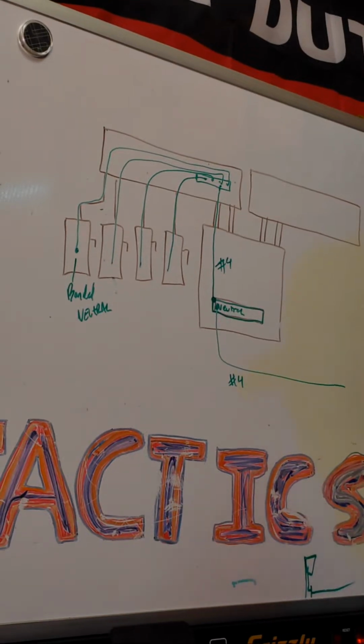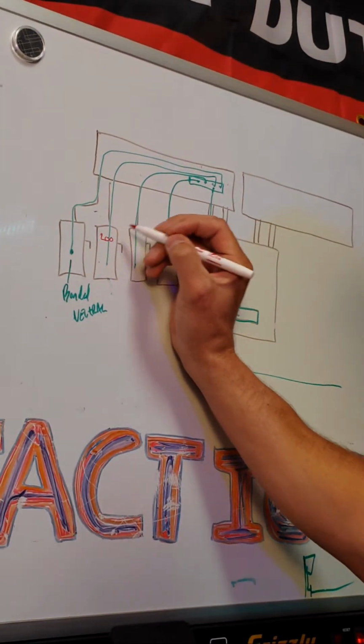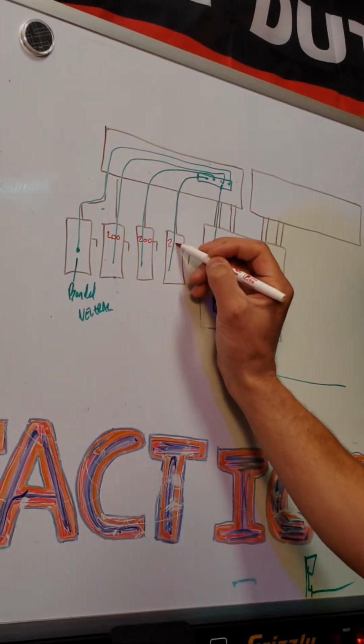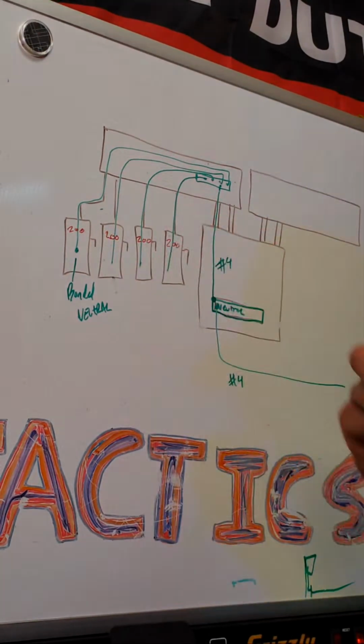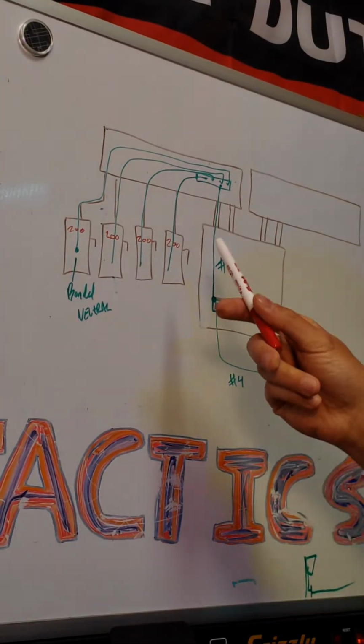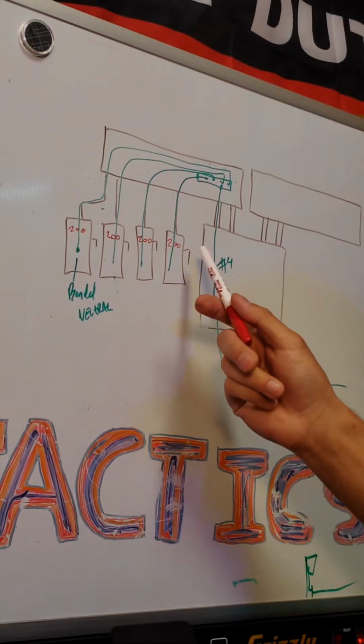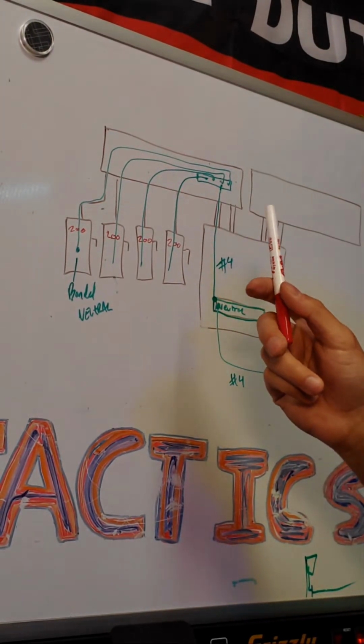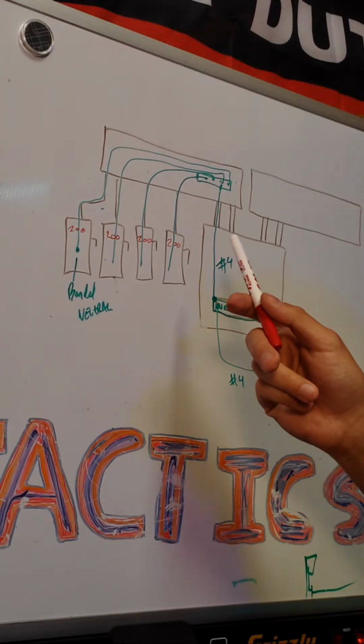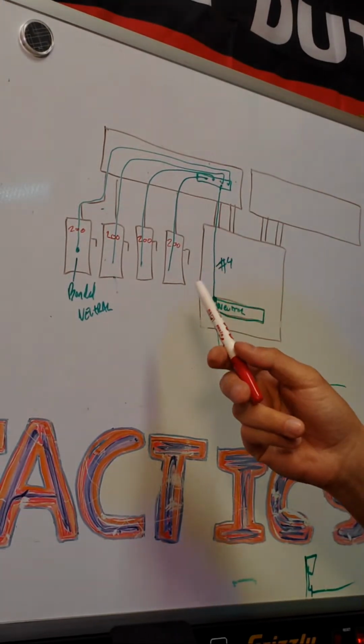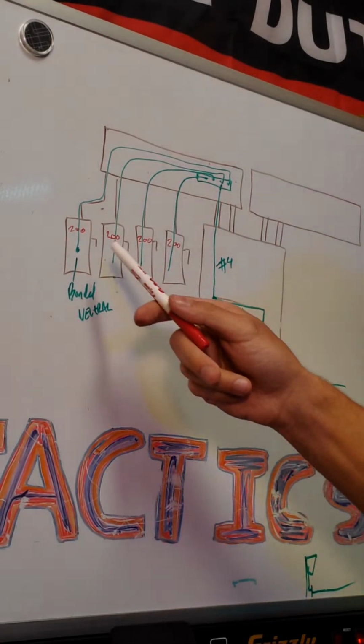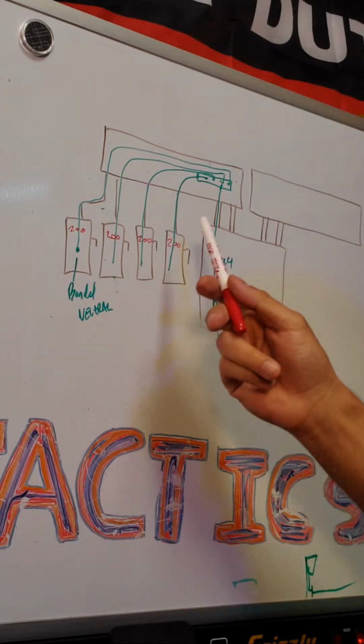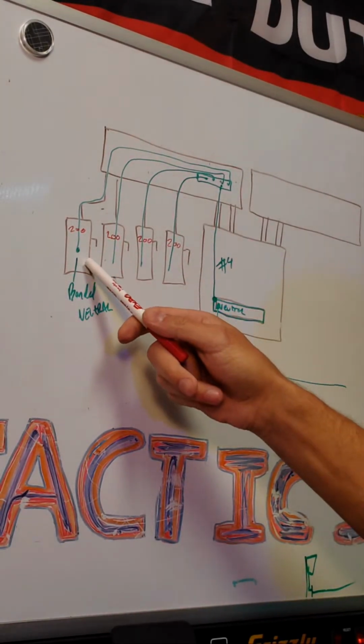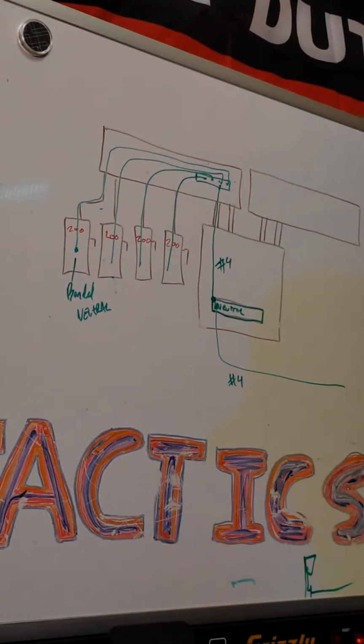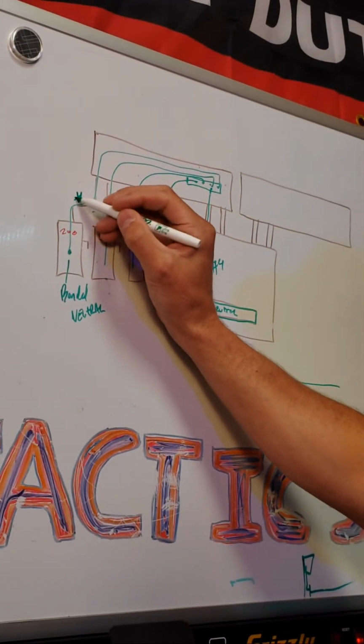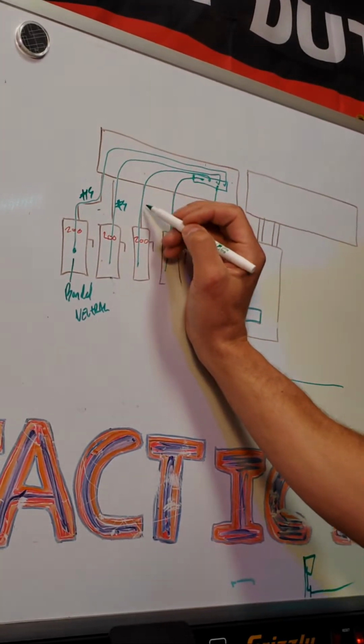If these are rated at 200 amps, these disconnects here, this is 200 amps. What we know about a service ground for 200 amps, it's not about the amperage, it's about the area of the largest ungrounded conductor. 250.66 says that 4-aught aluminum, 2-aught copper, 3-aught copper, whatever you got, you're going to need a number 4 for your service ground, which they did. It was number 4. So that was number 4. That was number 4.